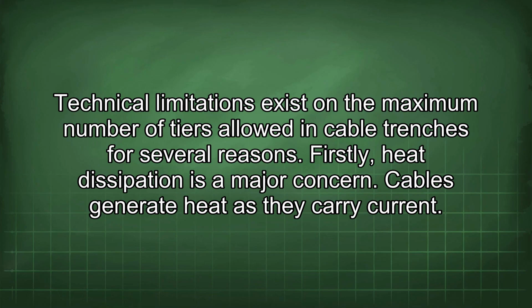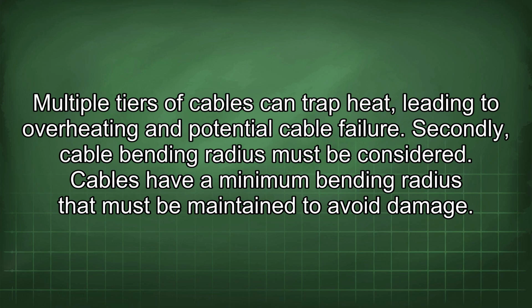Technical limitations exist in the maximum number of tiers allowed in cable trenches for several reasons. Firstly, heat dissipation is a major concern. Cables generate heat as they carry current. Multiple tiers of cables can trap heat, leading to overheating and potential cable failure.